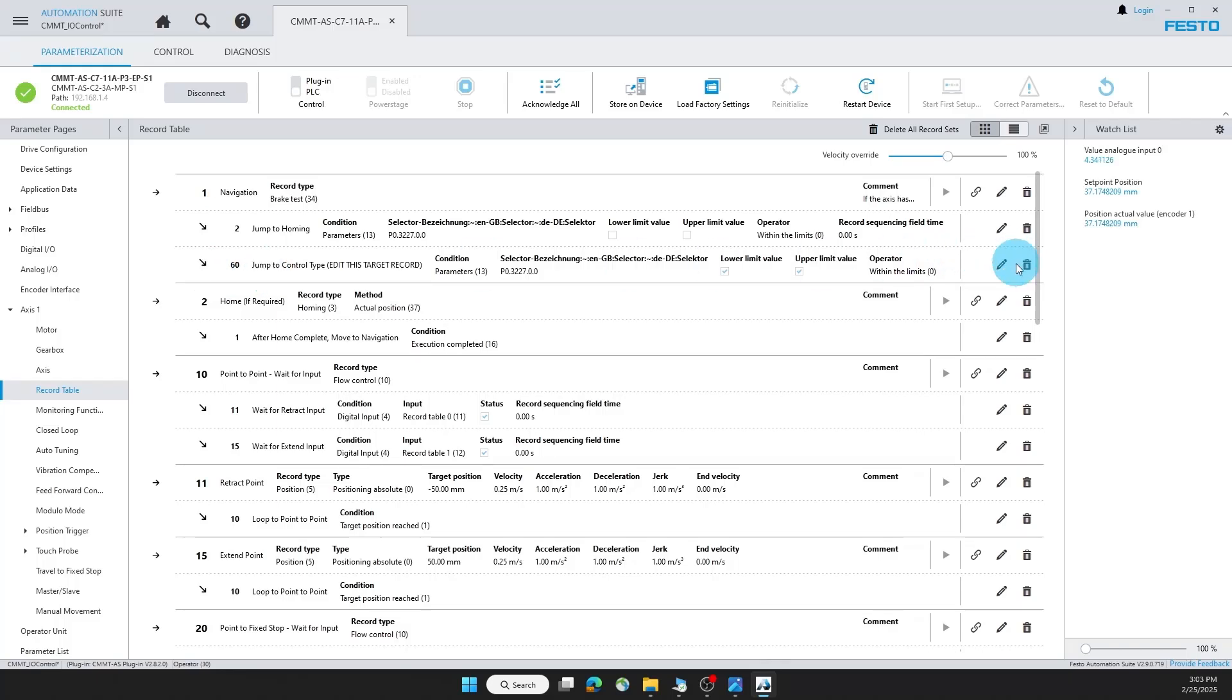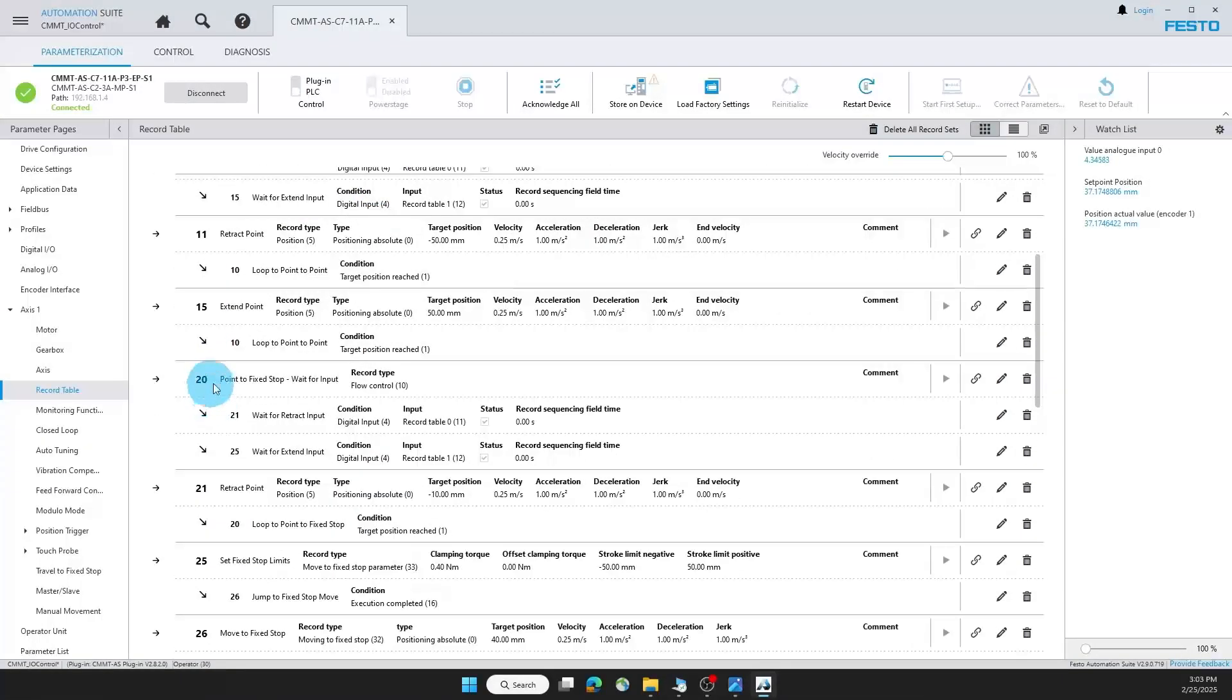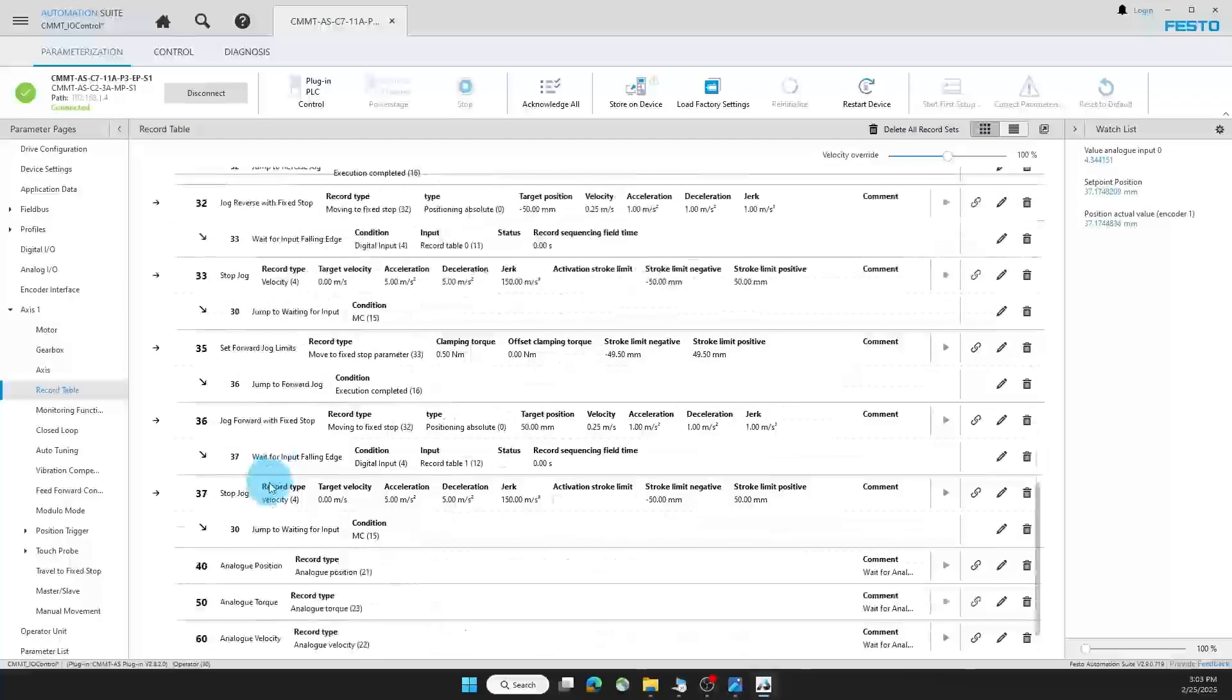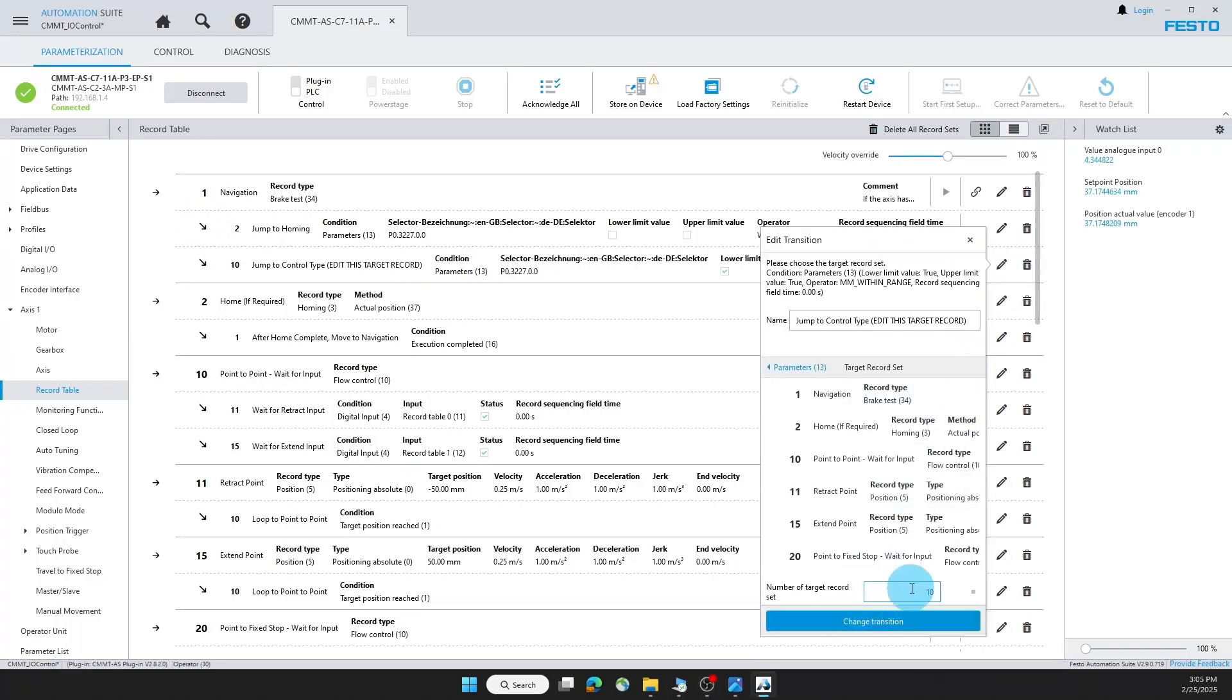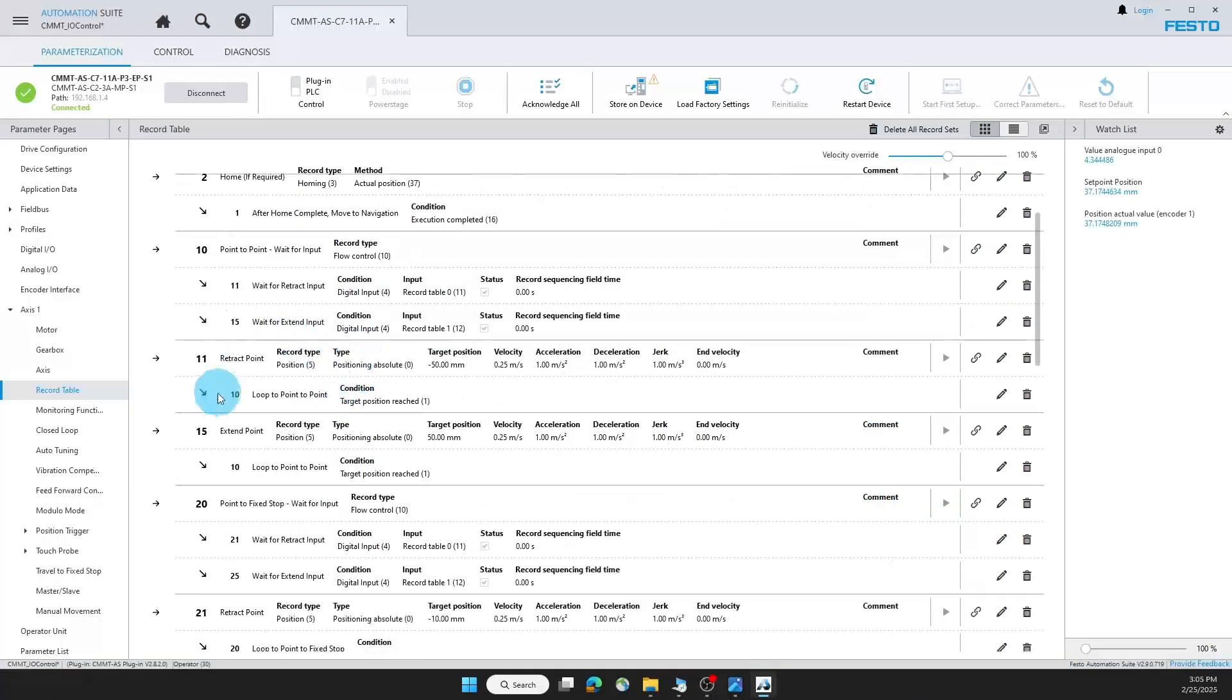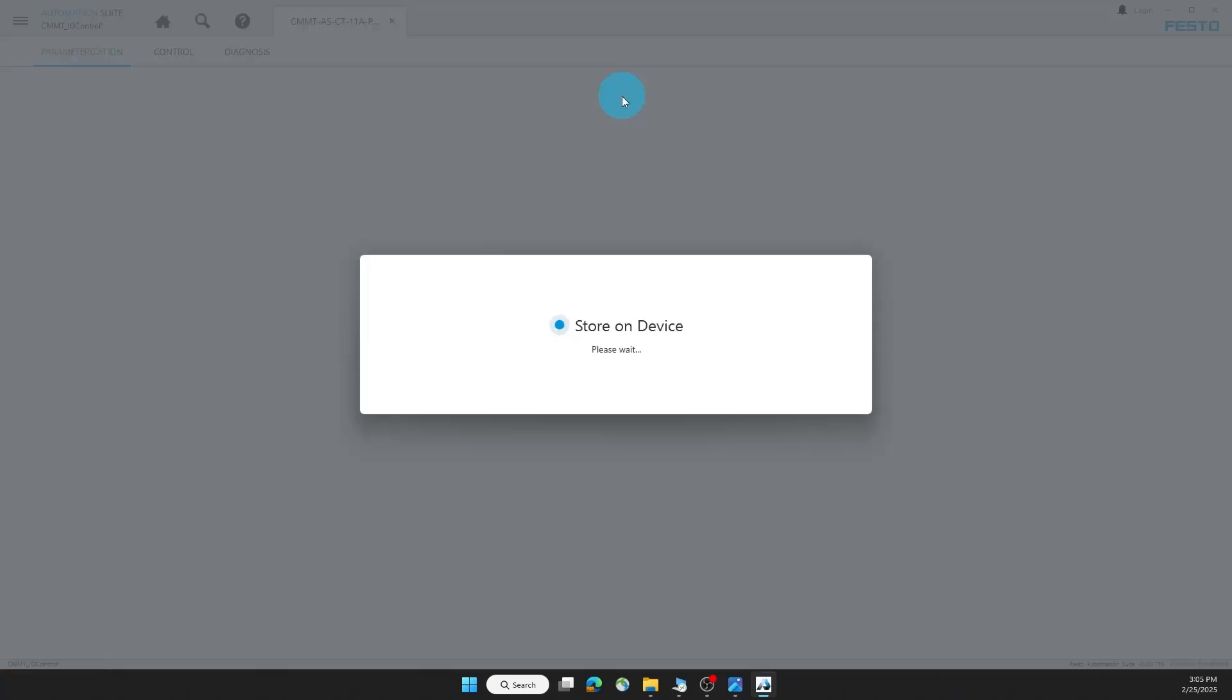In this transition you can edit which control type you want to move to. If I set it to 10, this will change to my point-to-point control. The other options are point to fix stop, bi-directional jog, analog position, analog torque, and analog velocity. Let's first look at point-to-point control. So under the transition for record one, I'll make sure this is set to 10. And then under this section, I have a retract point and an extend point. Here I can define positions, velocities, accelerations, decelerations, which can be different for each of the two positions.